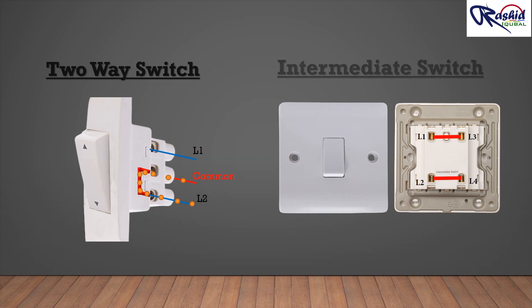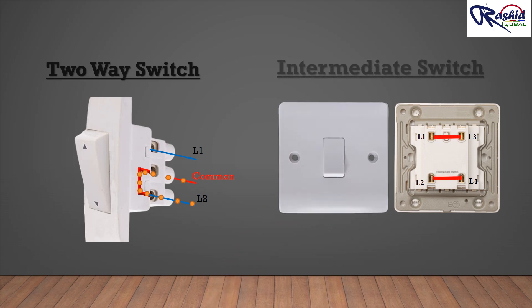In the intermediate switch, once the knob is downward, terminal L1 connects to terminal L4, and terminal L2 is connected to terminal L3. Alternatively, once the switch button is up, the terminal contacts will attach terminal L1 through terminal L3. Similarly, terminal L2 will connect through terminal L4, as shown in the following figure.